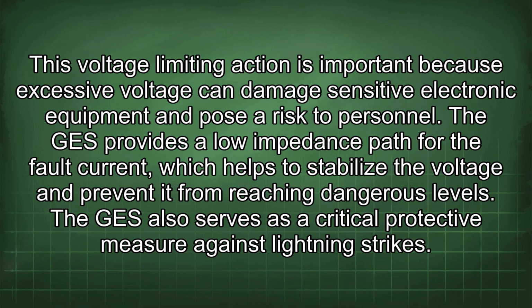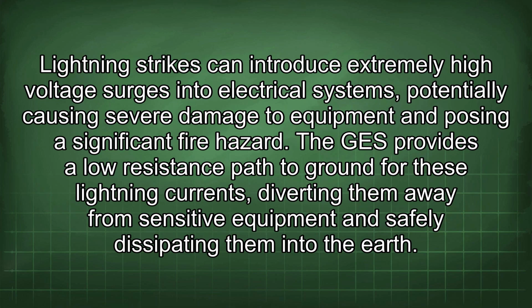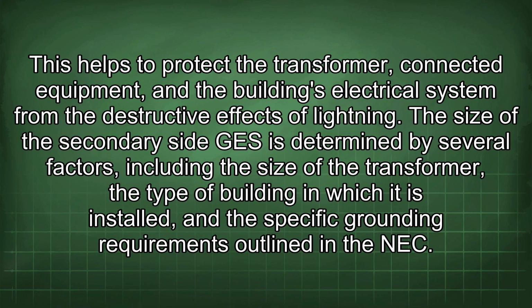from reaching dangerous levels. The GES also serves as a critical protective measure against lightning strikes. Lightning strikes can introduce extremely high voltage surges into electrical systems, potentially causing severe damage to equipment and posing a significant fire hazard. The GES provides a low resistance path to ground for these lightning currents, diverting them away from sensitive equipment and safely dissipating them into the earth. This helps to protect the transformer, connected equipment, and the building's electrical system from the destructive effects of lightning.